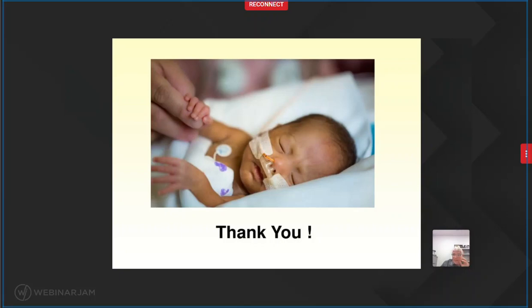The third one, which is the newest one, is NAVA. NAVA is definitely the one that has the fastest response time. It's extremely accurate and very, very sensitive. The problem with NAVA is that it's new, it's costly, and it's invasive. Also, it's difficult to position the probe correctly. Those are things that will get better with time as NAVA becomes more familiar. But I would say most of the neonatal ventilators now use flow.